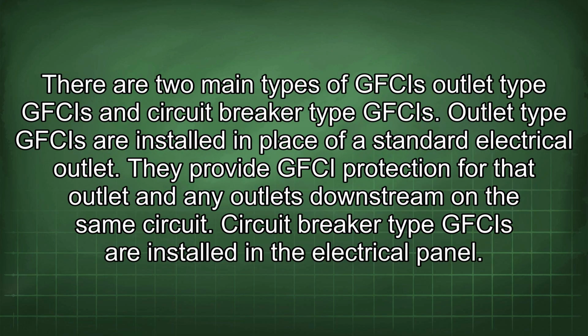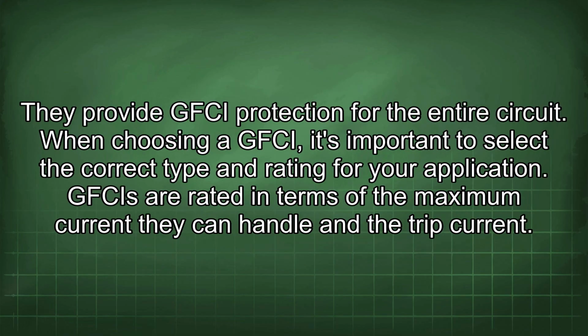There are two main types of GFCIs: outlet type GFCIs and circuit breaker type GFCIs. Outlet type GFCIs are installed in place of a standard electrical outlet. They provide GFCI protection for that outlet and any outlets downstream on the same circuit. Circuit breaker type GFCIs are installed in the electrical panel. They provide GFCI protection for the entire circuit.